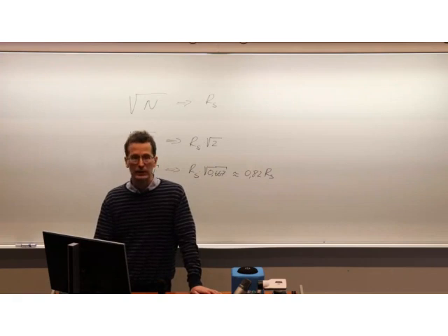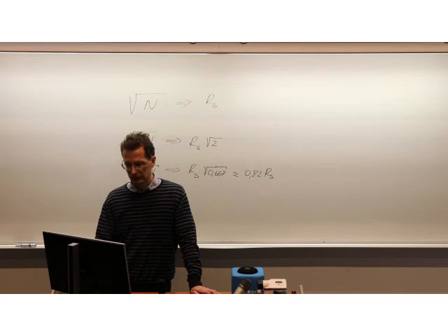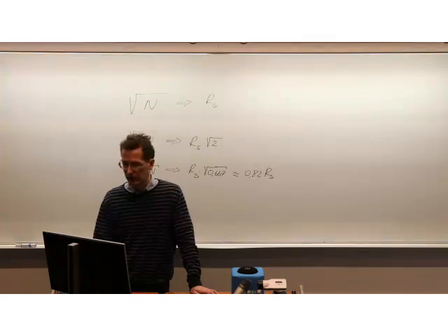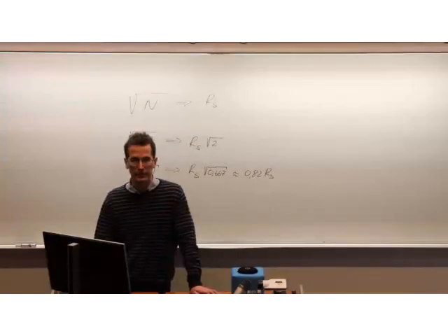And now we see that the number of theoretical plates is pretty much the same. Also, the peak resolution is quite the same. Well, the pressure is still high, but if our instrumentation can tolerate this, then that's fine. And as a result, we save 3 times the time. So instead of 15 minutes, now it's 5 minutes. So quite big savings in terms of time.